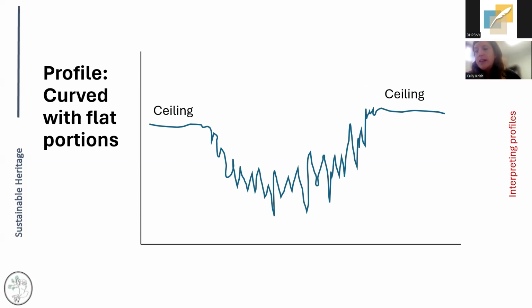The other thing I wanted to note with your summer ceilings and what you're maintaining is these can change over time. This gets into the importance of a long-term data monitoring program. If you notice that one year you were able to maintain 48, and the next year it was a ceiling of 50, and the next year it's a ceiling of 52, this can sometimes indicate that the system needs some maintenance or a component is failing, or even that there was just a change in the operation. So it's worth tracking over time and seeing how consistently you're able to maintain that ceiling, even from the perspective of monitoring the mechanical system's capabilities.